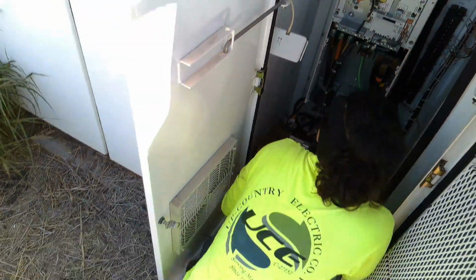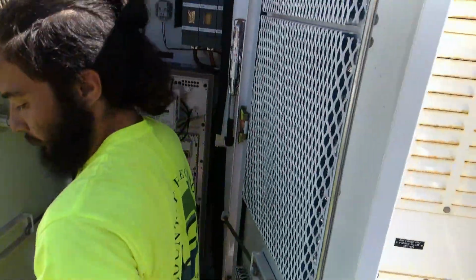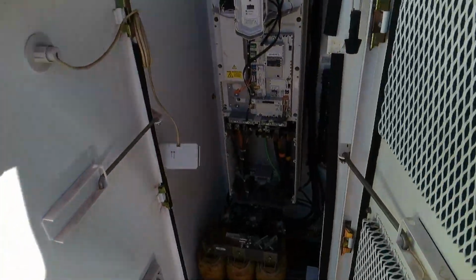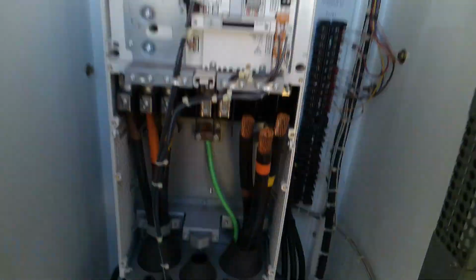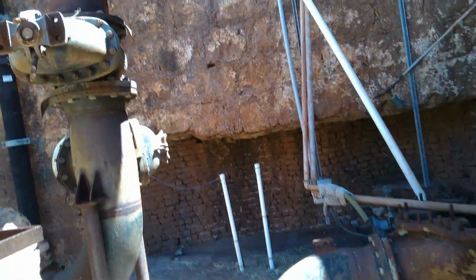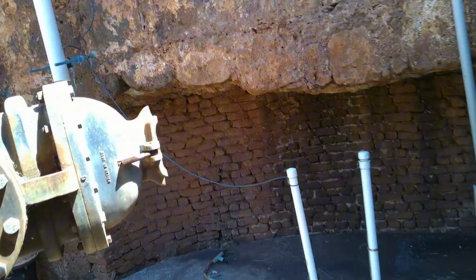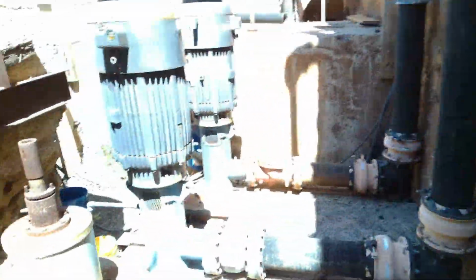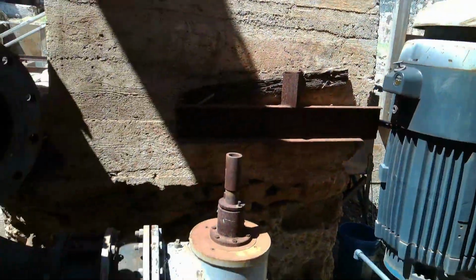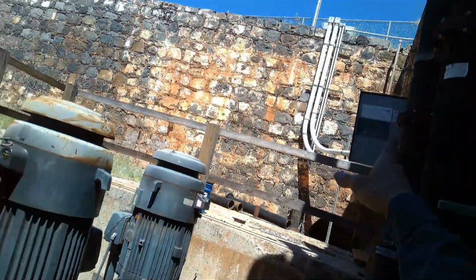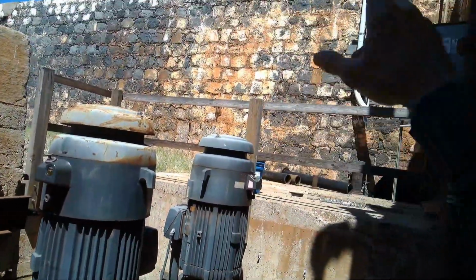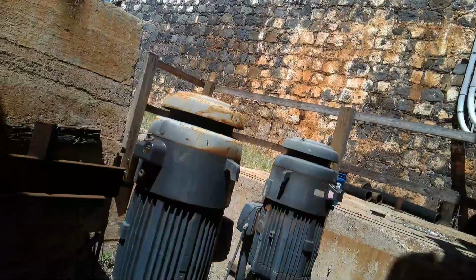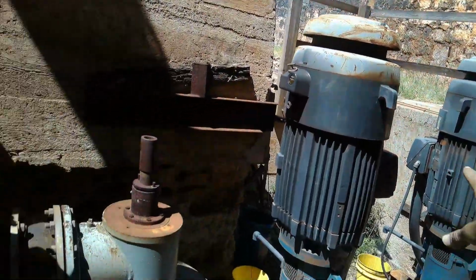Cool, you can hop out. I'm going to put it all back together. So yeah, that rules that out. Okay, so we checked between the disconnect and the motor and between the disconnect and the drive. Now I just want to be extra paranoid and look inside the pecker head.